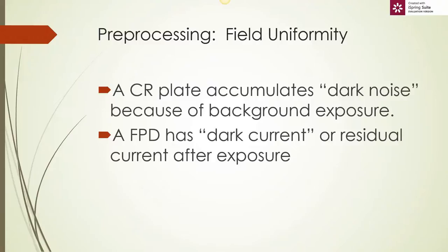Okay, residual current after exposure, to me that translates into afterglow or lag. And what those mean is that there is signal still being sent even though the X-ray beam has terminated. Anything that's being sent after that point obviously is unwanted, and that's precisely what we're talking about as an issue here.